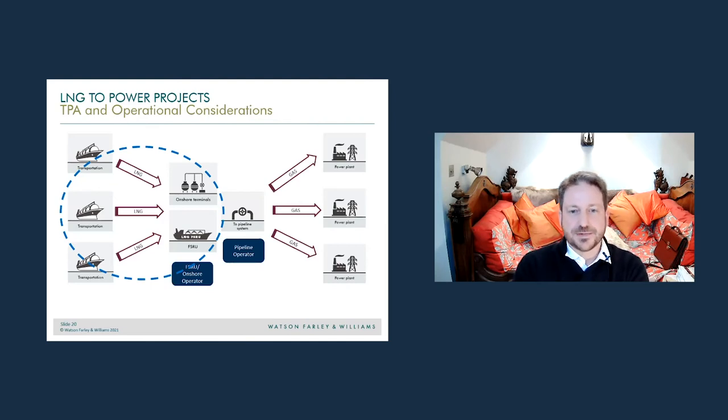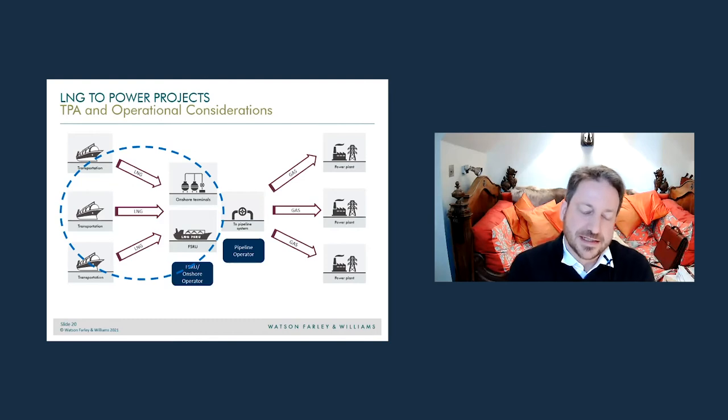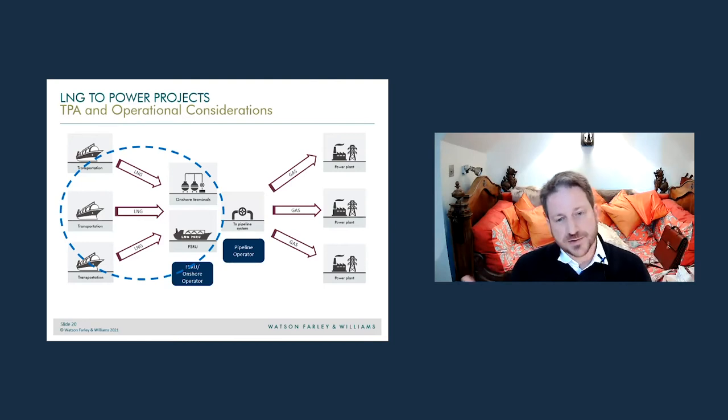And put very simply, this is usually that between 10% of the height in the tank and 70% of the height in the tank, the ship shouldn't set to sea while the liquid is at that level. So you need more time within that weather window to allow time to bring the vessel into a seaworthy state, all of which, of course, makes the delivery schedule more sensitive, or potentially more sensitive, with an FSRU.